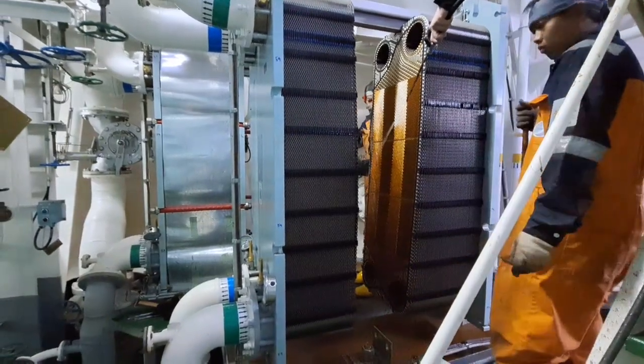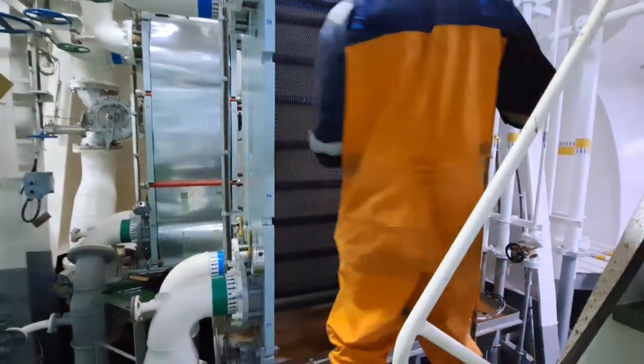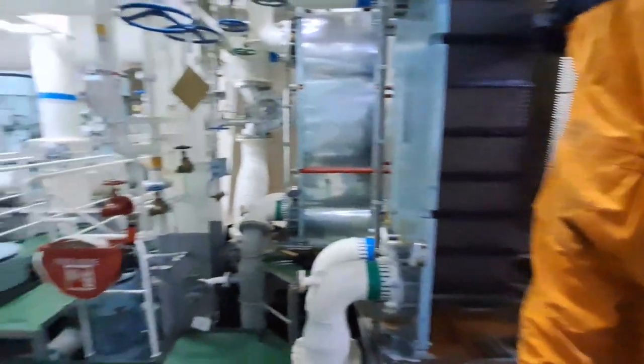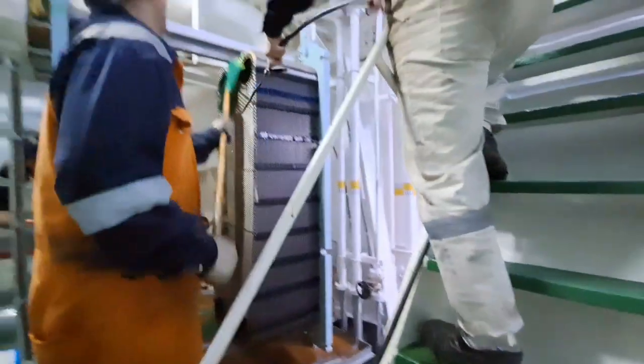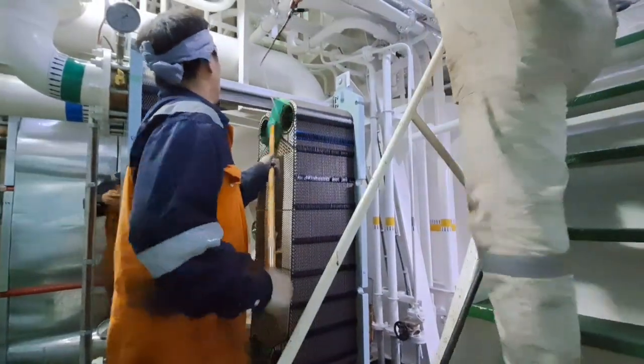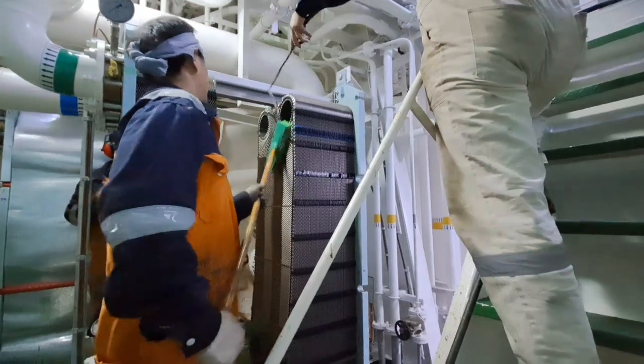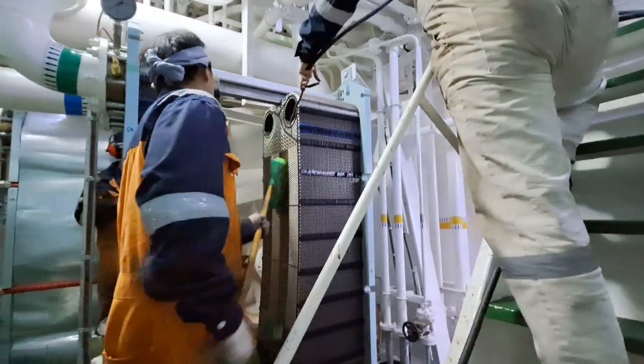Reassemble and tighten your plate heat exchanger to specification before returning it to service. If you don't have the replacement components on hand, you can wait for them to arrive. So you may simply close your plate exchanger and put it back into service while you wait.